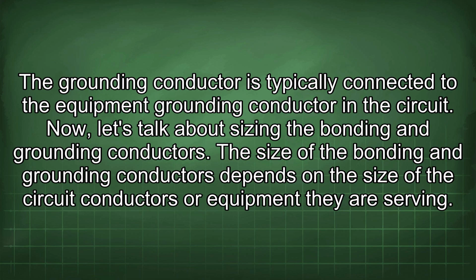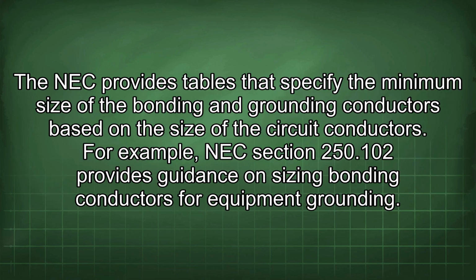Now let's talk about sizing the bonding and grounding conductors. The size of the bonding and grounding conductors depends on the size of the circuit conductors or equipment they are serving. The NEC provides tables that specify the minimum size of the bonding and grounding conductors based on the size of the circuit conductors.